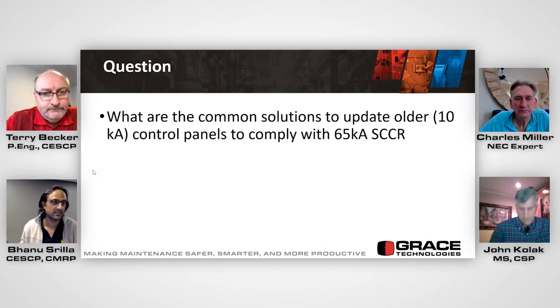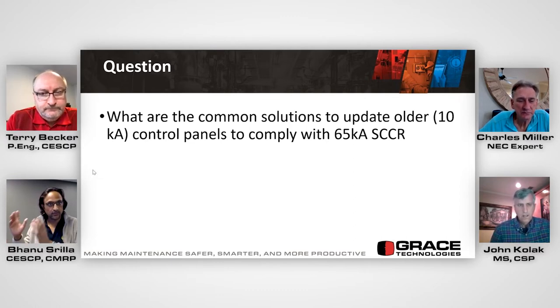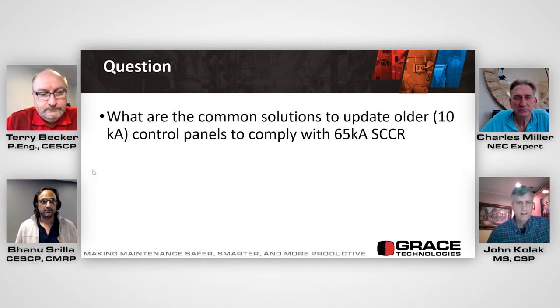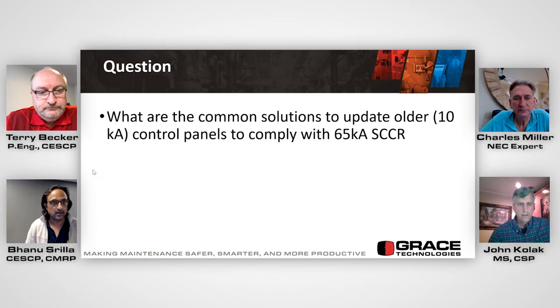I'm assuming the question is: if something has changed in the fault current of their system, if someone installed a 10 kA panel decades ago, and something changed significantly within their premises, how do they upgrade? It's basically increasing your breaker fault clearing, the short circuit current ratings, and then the clearing times, going from that angle.